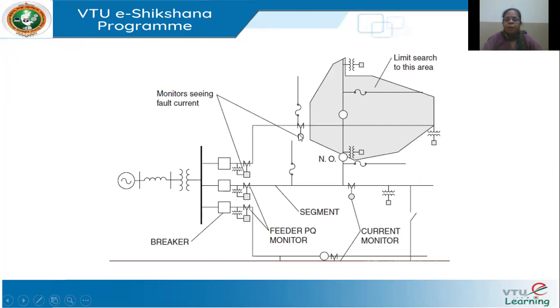So you see here, there are two monitoring currents. So looking at these fault currents, I draw an area. Okay, I draw an area. What does this mean? This means that my fault is somewhere within this area to give rise to these fault currents. So then I stop my search in other segments. I'm not interested in other segments because they are not affected. So I don't use the variables in the other segment for my optimization, because optimization has to be done quickly, right? I may need to take a control action. So once we see the fault monitors in some, then this will narrow down. You can draw a segment and narrow down the search for your fault location. Okay. And then make an estimate only of that particular area.